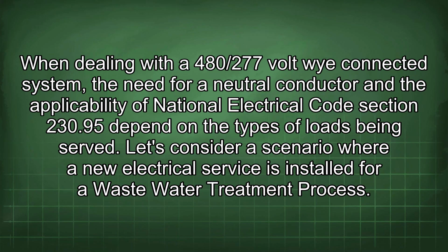When dealing with a 480/277 volt Y-connected system, the need for a neutral conductor and the applicability of National Electrical Code Section 230.95 depend on the types of loads being served. Let's consider a scenario where a new electrical service is installed for a wastewater treatment process.